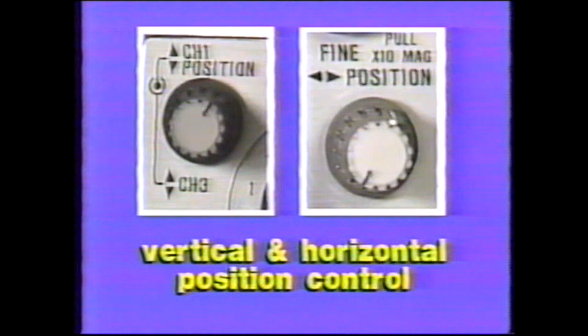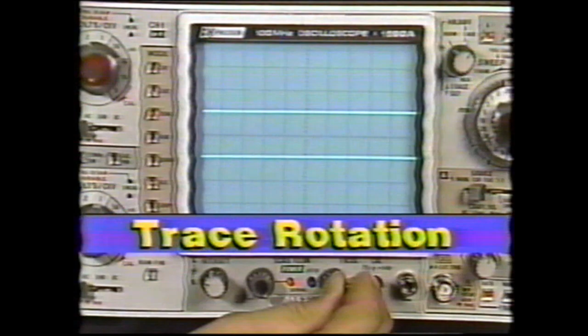The vertical and horizontal position controls are used for locating and positioning the channels on the display. Before using any oscilloscope, check the trace location, DC balance, and calibration. To check trace rotation, select the appropriate mode switch and ground that channel's input. Make certain the trace is straight, horizontally, across the CRT. If the traces are not straight, compensate by utilizing the trace rotation screwdriver adjustment.